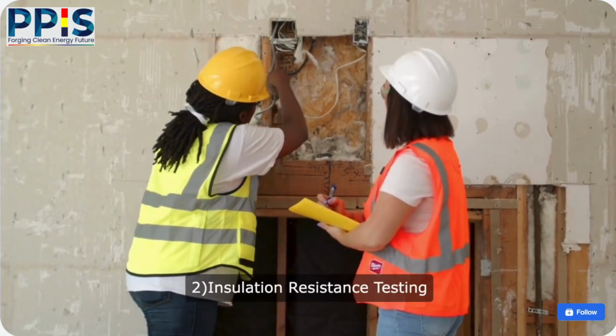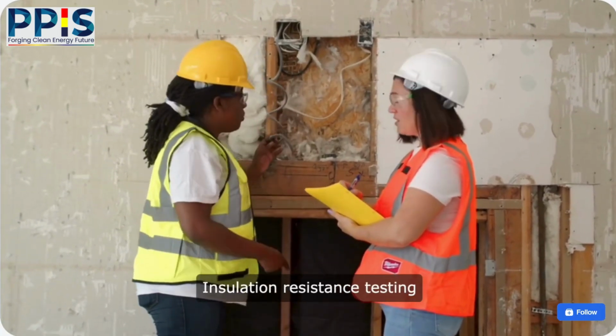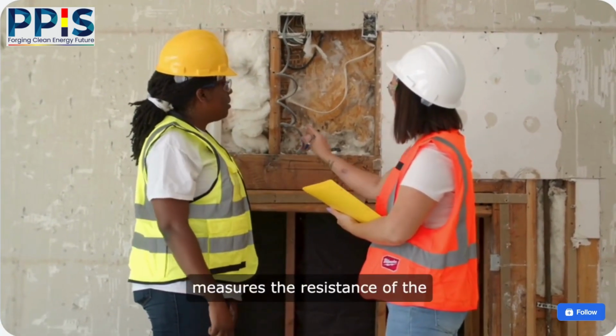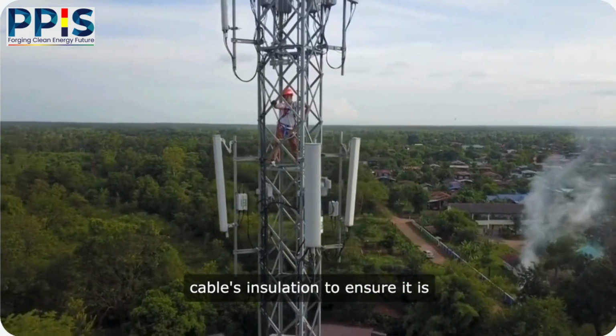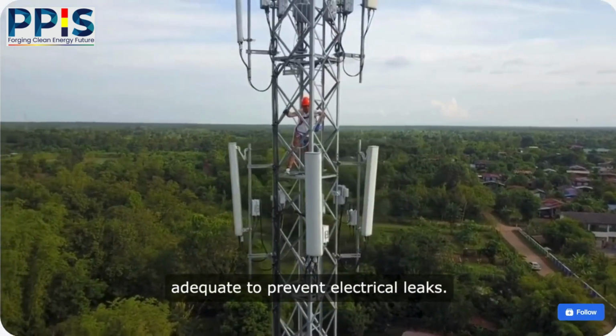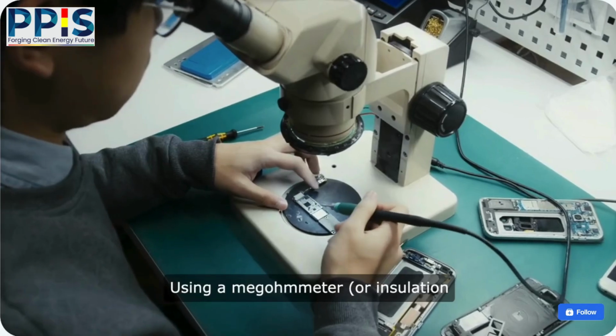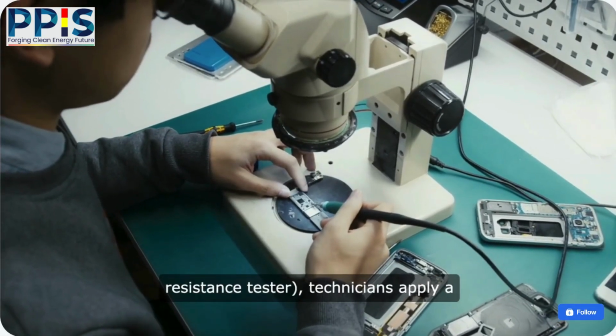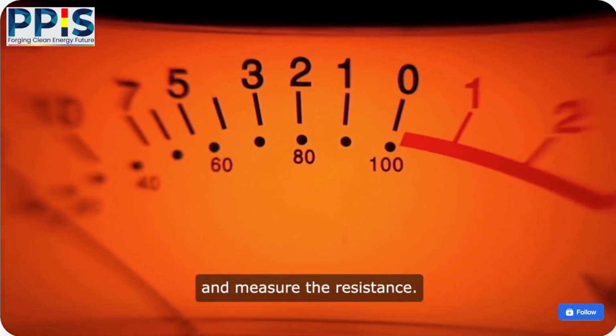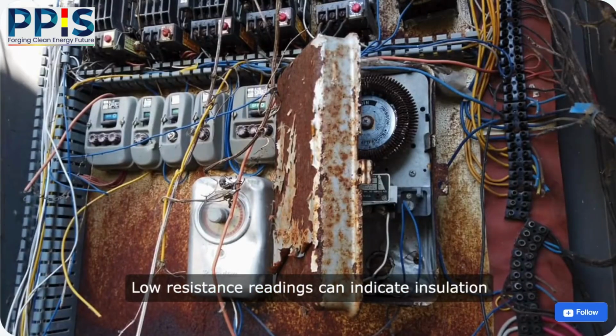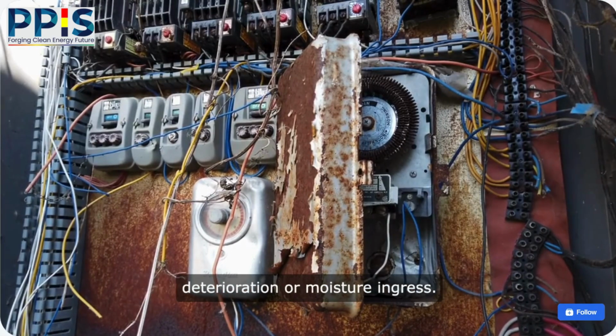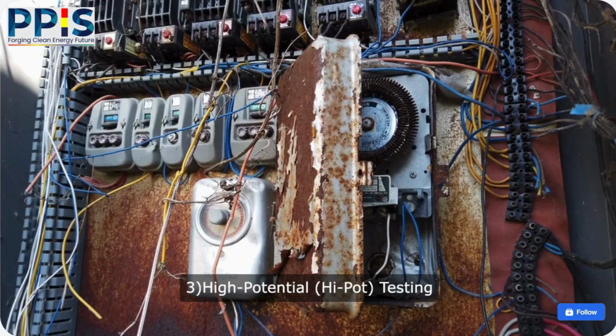2. Insulation resistance testing. Insulation resistance testing measures the resistance of the cable's insulation to ensure it is adequate to prevent electrical leaks. Using a megohmmeter or insulation resistance tester, technicians apply a high voltage to the cable and measure the resistance. Low resistance readings can indicate insulation deterioration or moisture ingress.